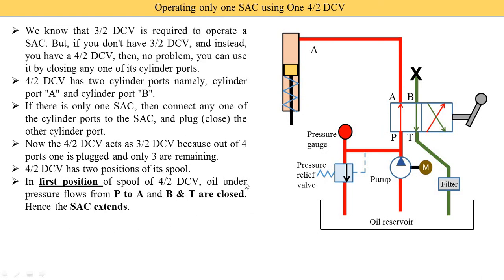B and T are closed. Here you see the B port is closed. Suppose this B port were connected to another cylinder — oil from that cylinder would enter port B and go from B to T to the return. But here port B is blocked, so no oil enters the B port, meaning no oil reaches the T port either. That is why B and T are closed.